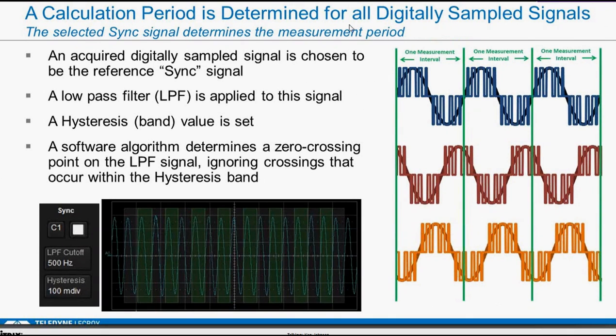And then the second thing we have to do is determine a calculation period. Again, this approach is reasonably widely used. We basically apply a zero-crossing detection algorithm to the signal we're measuring, and we calculate a period. So for instance, if this is my signal here, and it can be a very ugly signal, with proper filtering and some hysteresis settings, you can quite easily get a very clean zero-crossing determination. So basically, we say, here's the zero-crossing, positive going, here's the zero-crossing, positive going, here's another one. So this is one measurement interval, this is another, and so on.